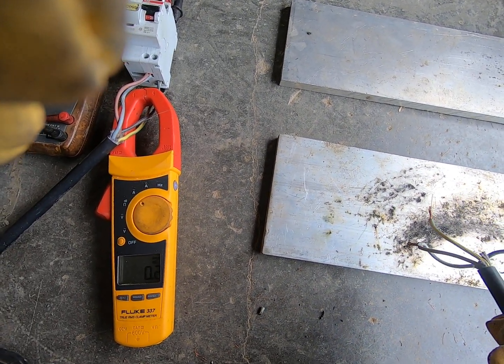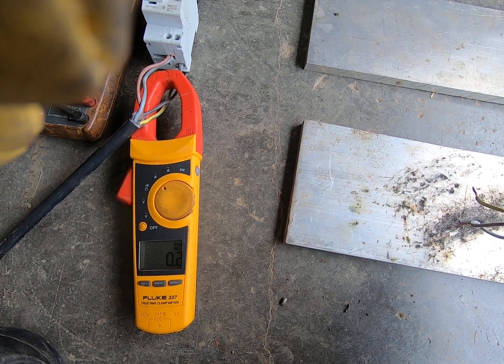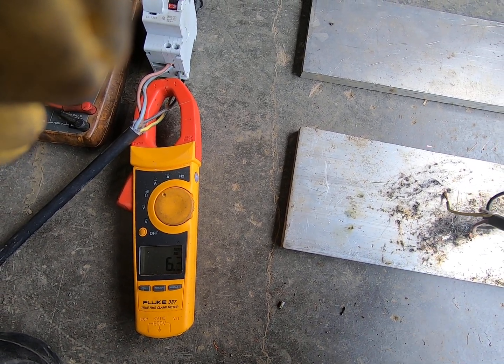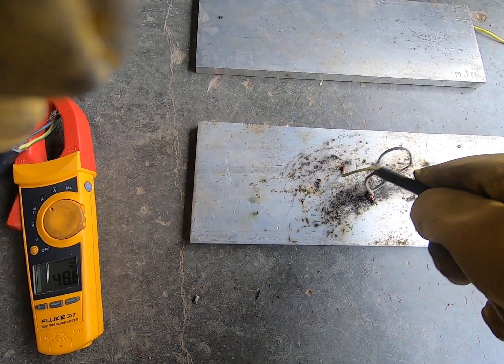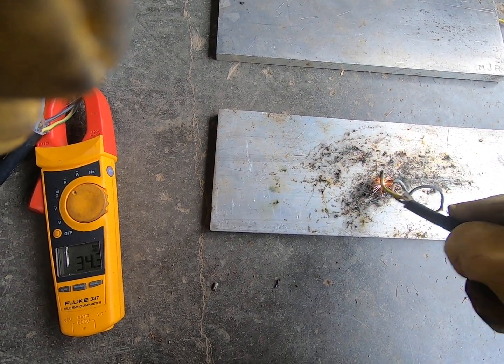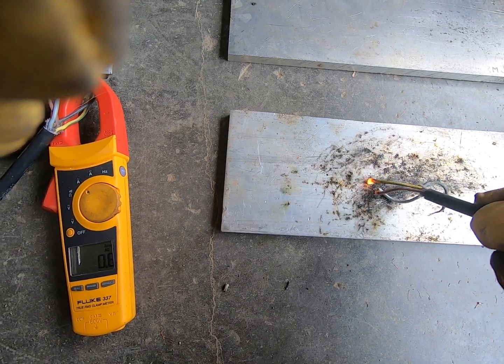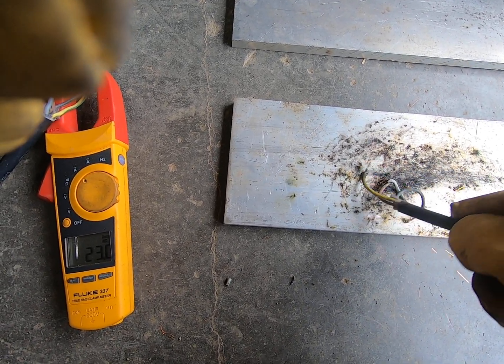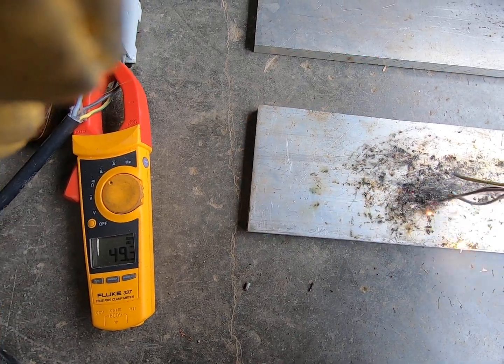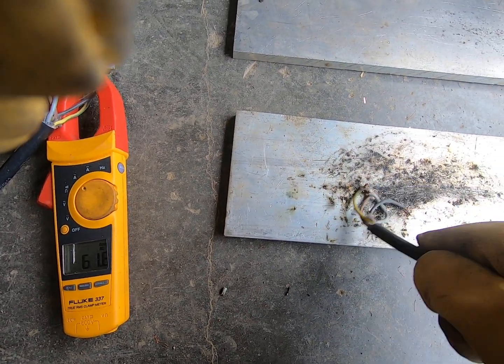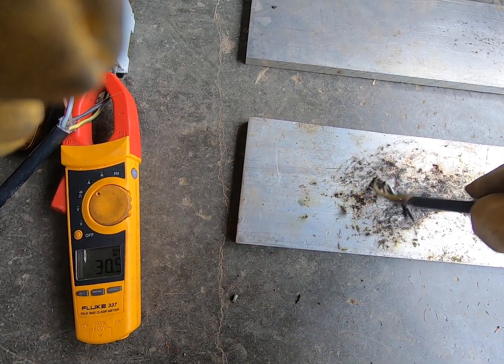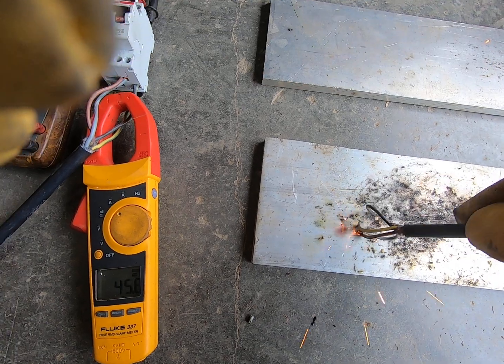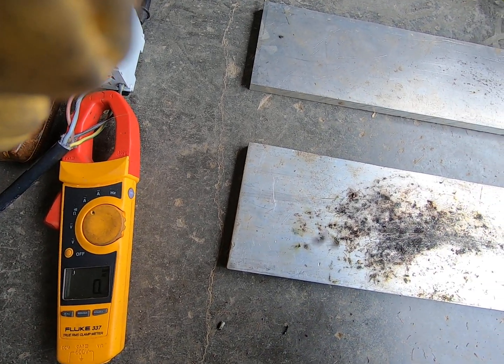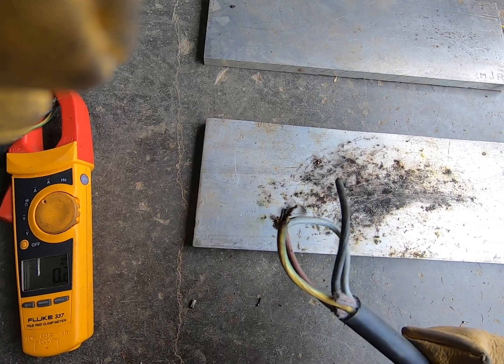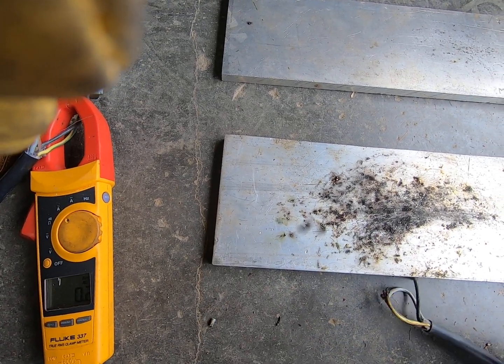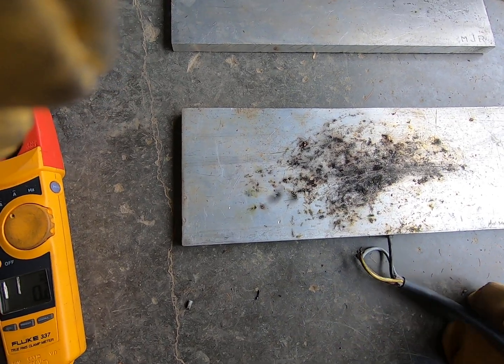One more last test here is just a dead short. Now if we had a situation where maybe the cable's not dead shorted and it's just intermittently arcing, what you'll notice is it becomes a bit of an arc welder, and it gets much hotter. And there you can see the cable's actually on fire. Obviously with this intermittent shorting, the breaker doesn't trip immediately. So we get some decent sparks, some decent arcs, a little bit of fire there.